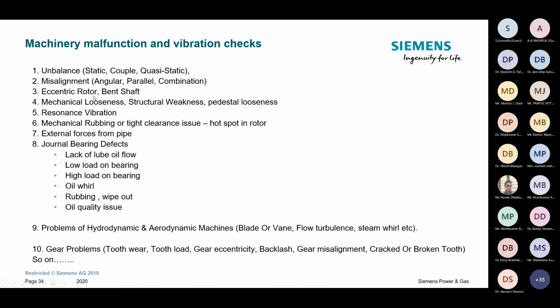By the way, the mass of the rotor is almost 70 ton or 80 ton. So an 80-ton rotor is rotating at 3000 RPM or 3600 RPM. The forces on the bearing pedestal or bearings will be very huge. So any eccentricity in the rotor due to thermal bow will also result in vibration. The other reason is a bent shaft.